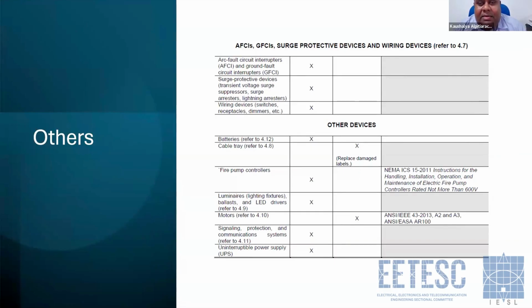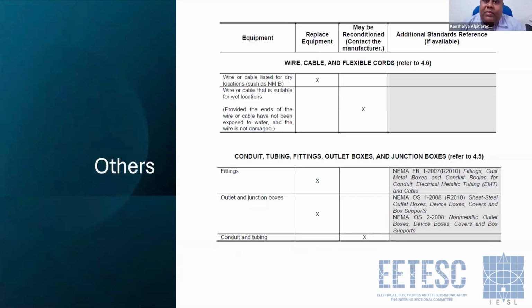If this is a hospital and the UPS is provided for your operation theater, if that doesn't work, what is the purpose of having it? If the UPSs are catering to your data center, if it is not working, what's the purpose of having it? So replace. Wires, cables, flexible cords. Wires or cables listed for dry locations, replace.